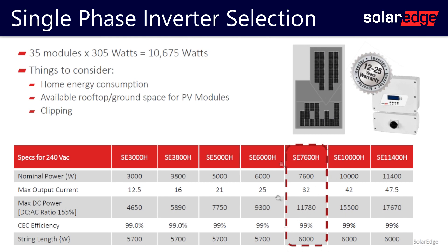The maximum output current of the 7.6 kilowatt inverter is 32 amps. We said the main service entrance is 200-amp service, so without derating the main or doing a line-side tap, the maximum breaker size for the back-feeding breaker is 40 amps — which is ideally sized for this 7.6 kilowatt inverter. If you wanted to upgrade to the 10 kilowatt or 11.4 kilowatt, you may have to consider derating the main or a line-side tap.